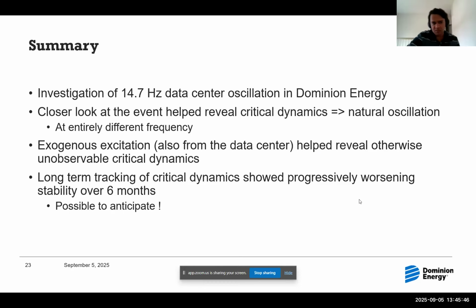To summarize, we looked into a 14.7 hertz data center oscillation, but if you look closely, it wasn't a forced oscillation — it was a natural control mode local to the data center that became unstable. We could only make this connection because the data center is also a source of exogenous excitation that excites this particular mode, enabling us to study and track it. Otherwise, it's so stable that we can't really estimate it from ambient data. We saw it progressively getting worse from a stability standpoint over a period of 6 months, and then we saw the oscillation, which means there was actually a chance at anticipating this particular event.